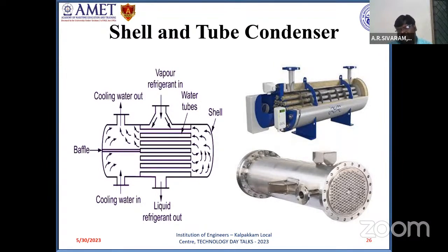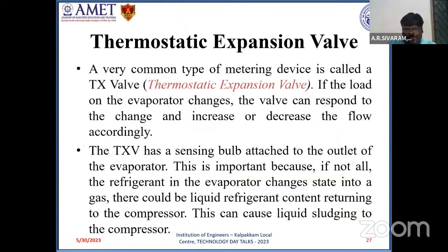Even for marine applications, a shell and tube water cooled condenser is employed in the accommodation part. Earlier they were using seawater, but since seawater causes corrosion, nowadays they are using fresh water in shell and tube condensers. This can be used from 50 tons to 500 tons. So for systems with very high refrigeration capacity, a shell and tube water cooled condenser can be employed. Evaporative condensers use both air and water.